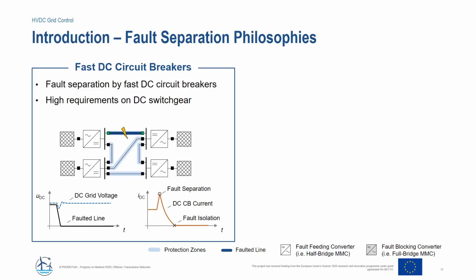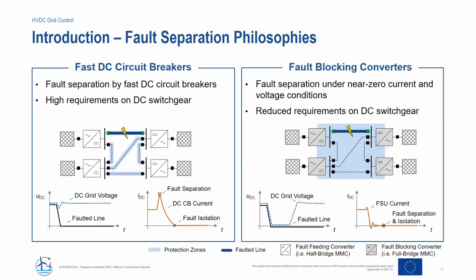And in order to separate this fault, the circuit breakers at the faulted line ends have to separate under very high currents, and therefore also they have to absorb a lot of energy during this interruption process. So overall, the requirements on the DC switchgear are relatively high.